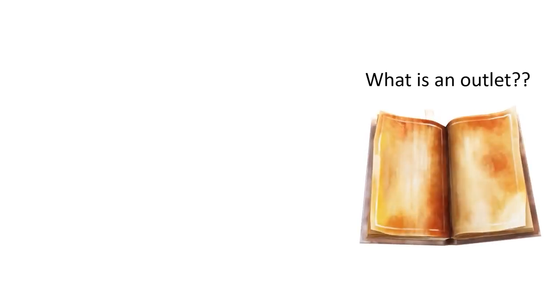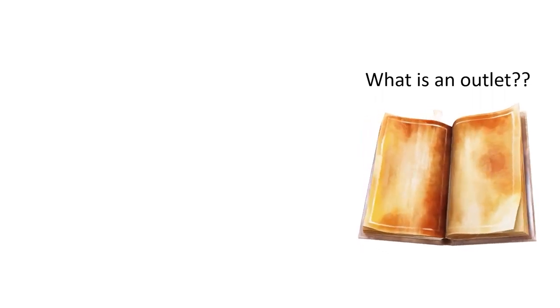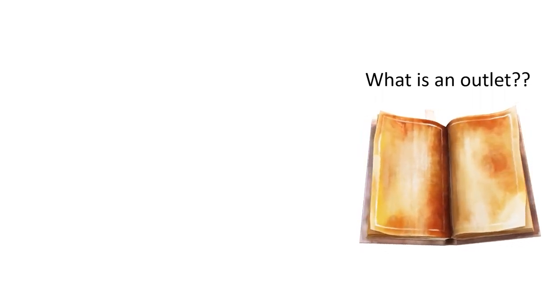To answer this question, we're going to have to define what an outlet is. The best place to define things in the NEC is Article 100, which contains code-wide definitions. Let's find out if there is a definition for outlet — and there is. It says: a point on the wiring system at which current is taken to supply utilization equipment.